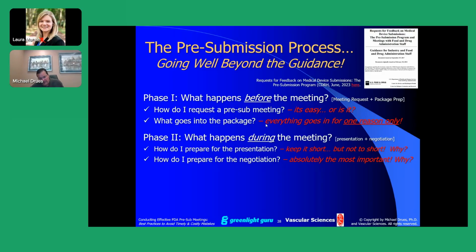And the other reason, let's be honest, is unfortunately there are those FDA reviewers that will not read your pre-submission package until literally they are walking into the room, or literally logging onto the Zoom if it's a remote call. I wish I could tell you that never happens. It does happen. So rather than being naive and thinking that these things don't happen, I will spend a bit of time, again, not a lot, recapping what the device does, how it works, its mechanism of action. I will recap the labeling, the intended use, the indications for use, and so on and so on.